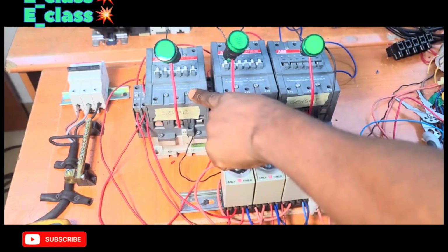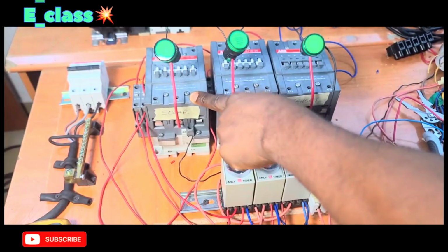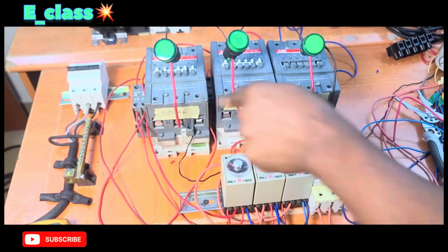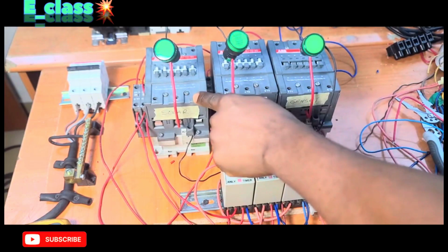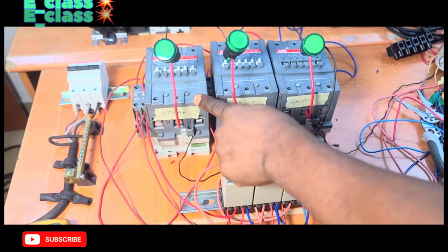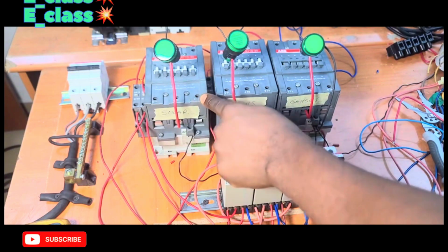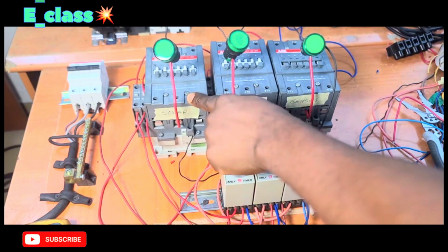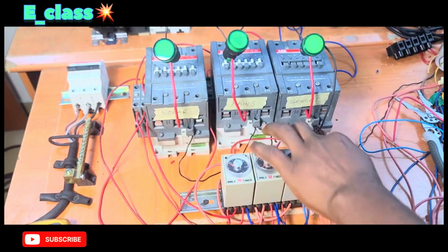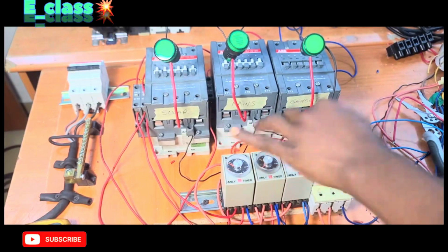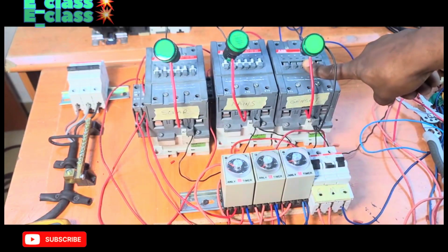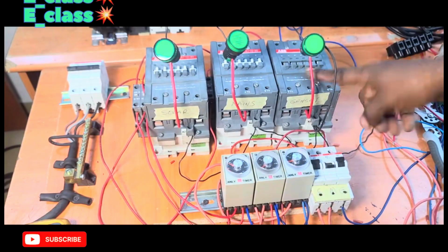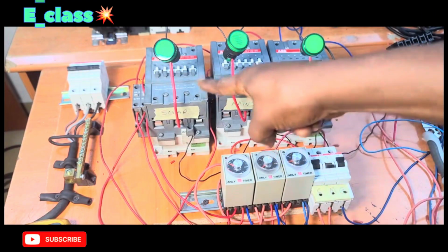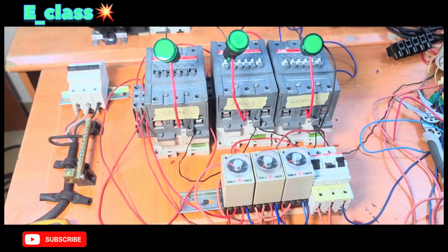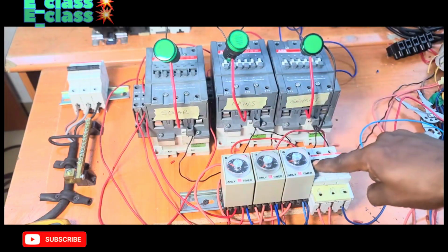If solar is up and active, we expect that this one will cut off immediately and this one delays for some seconds and then energizes. But that is not the case here. Let us energize this one. Let us activate solar by putting on this one. You see, this one's supposed to trip immediately, but it won't until after the delay here. This is not what we want. We want this one to cut off immediately when mains is restored.